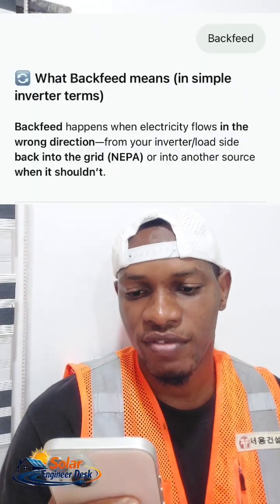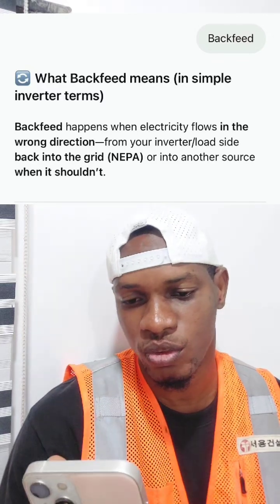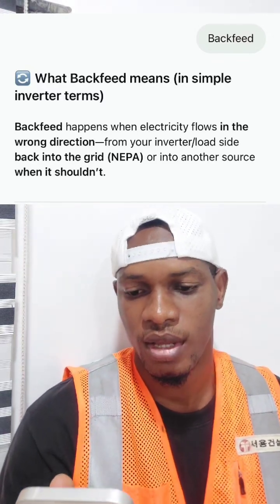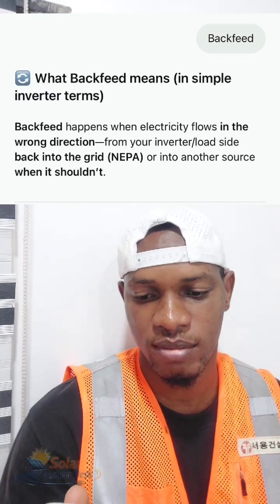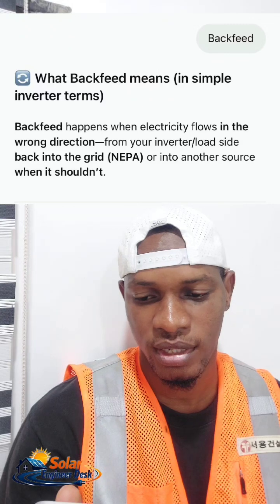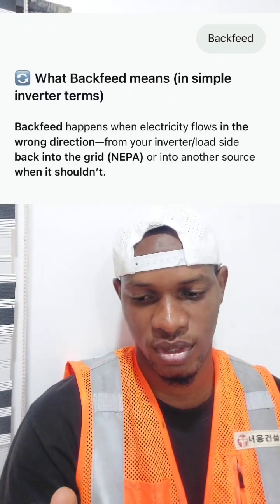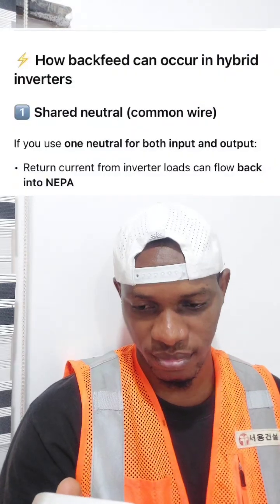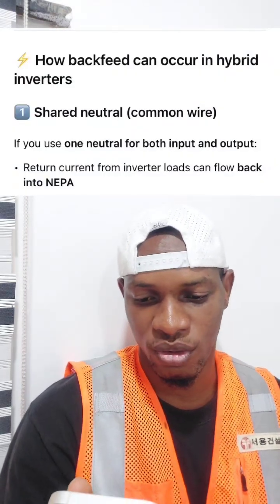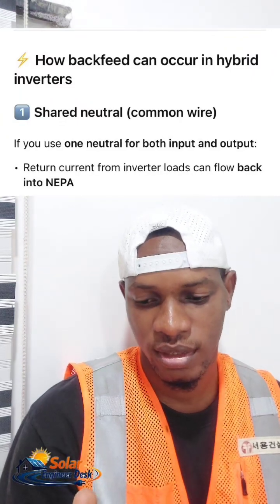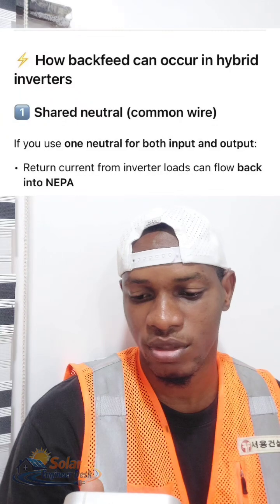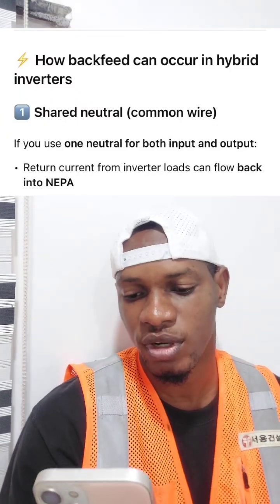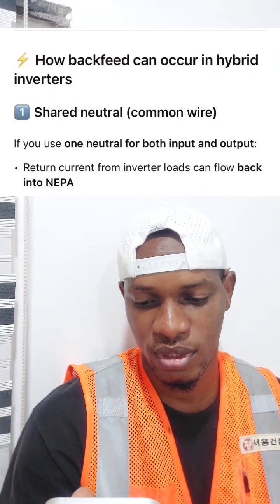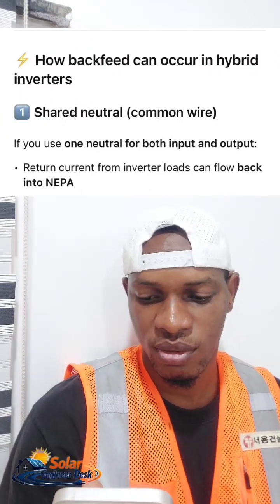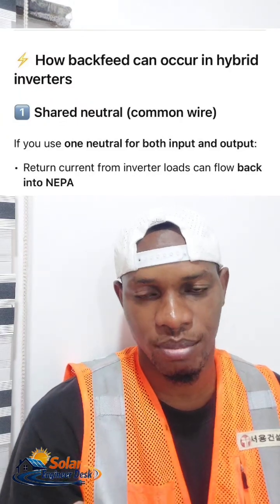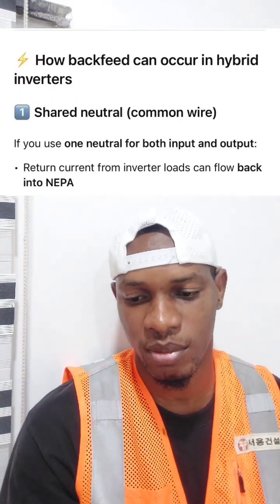Now, backfeed happens when electricity flows in the wrong direction. That is, from your inverter or load side back into the grid or another inverter source when it shouldn't. The main reason why backfeed occurs in a hybrid inverter is, one, when you use a shared neutral, that means a common wire. If you use one neutral for both input and output, the return current from the inverter load can flow back into NEPA. That is one of the reasons why backfeed happens.